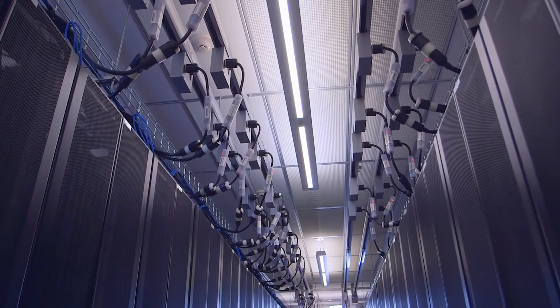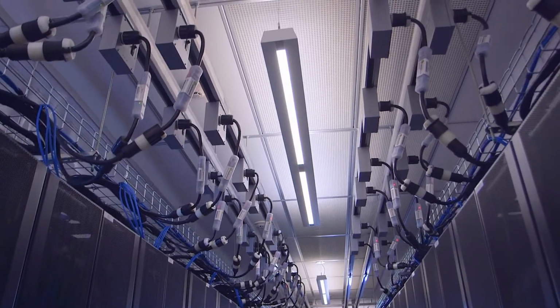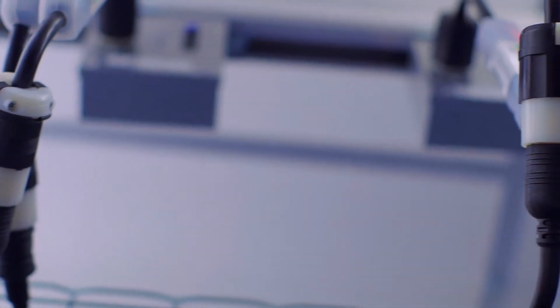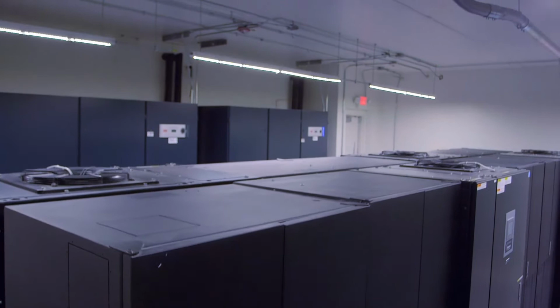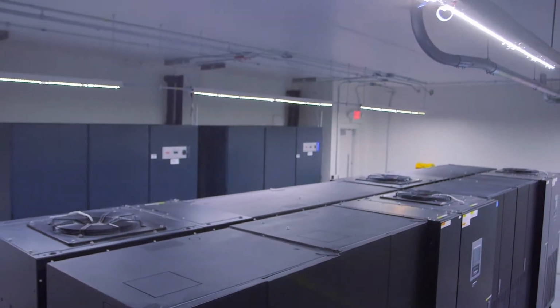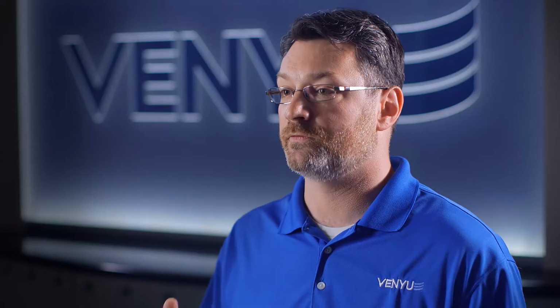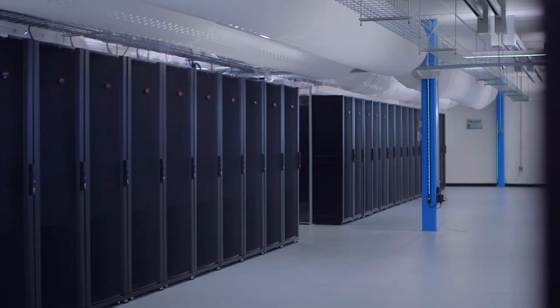Power is delivered to the rack from a Starline bus system located above the rack, and they go back to a UPS system with 4 separate UPSs. So all the racks in the data center have access to one of 6 different configurations of those 4 UPS subsystems.